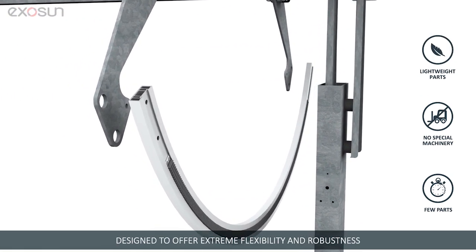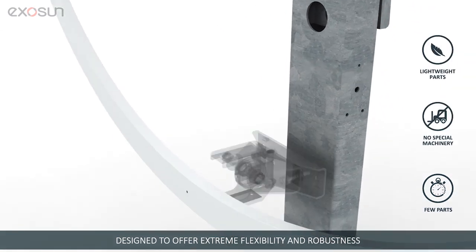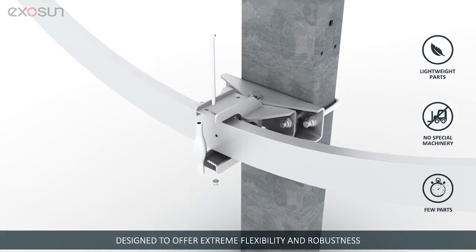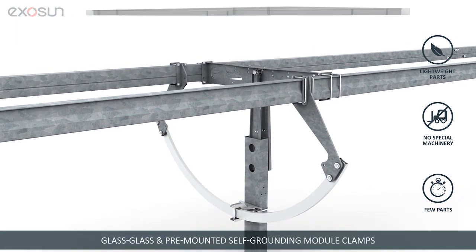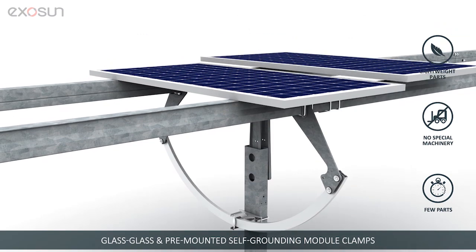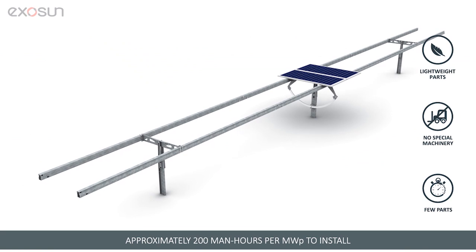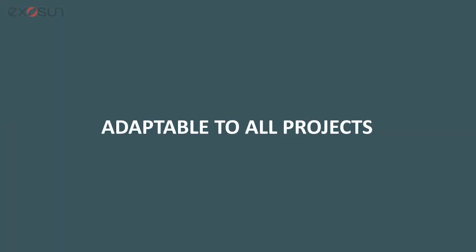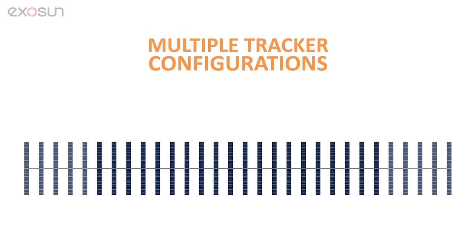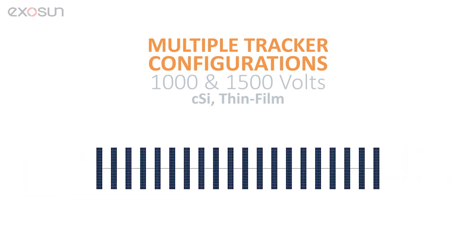Its extremely robust parts also offer flexible installation tolerances. Adaptable to glass-glass and framed modules, pre-mounted self-grounding module clamps facilitate installation. Exotrack HZ v2 is simple and fast to install in just 200 man-hours per megawatt peak. To meet all project needs, it is available in multiple 1,000 and 1,500 volt configurations for CSI and thin film modules.